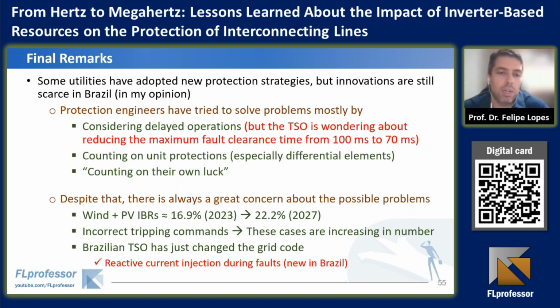This is why the Brazilian TSO has just changed the grid codes. Previously there was no requirement to inject reactive current, nor negative sequence current, but now in Brazil reactive current injection is required by the TSO. It is new in Brazil.